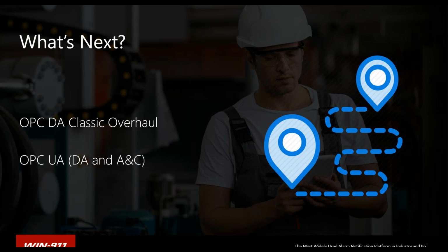We're also working on OPC UA modules so that we can connect to UA servers for DA and alarms and conditions. So alarms and conditions, or some people call it alarm events, it functions more like you subscribe to a server and you just get the alarms. It's not a traditional OPC connection where you're importing a bunch of items and setting up alarms on those items. It's much easier to set up because you're just subscribing to alarms and they just automatically come in. So we're working hard on those things.